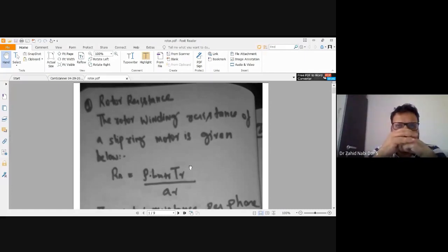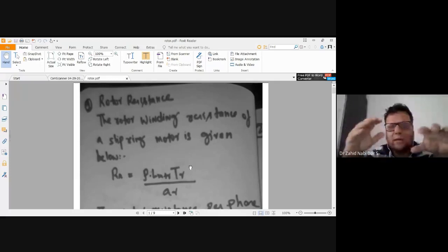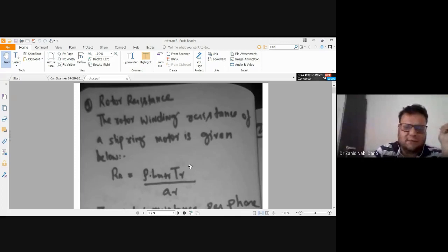And how do we calculate the rotor resistance? Each one of you knows that the loss as far as the induction motor is concerned would be I square R. But as far as the bars and rings are concerned, one end ring is at the top and another is at the bottom. So one at top, another at bottom, so it would be twice Ie square into Re. Now we are establishing this particular thing.